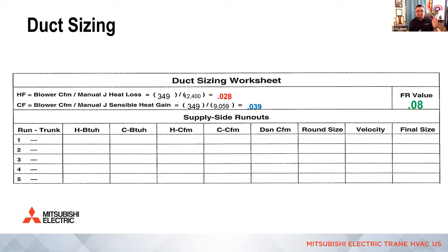Then we're just going to list the rooms that we're going to service with this air handler. So this particular unit is going to service a master bedroom, a bathroom, and then a second bedroom. So probably, let's say upstairs of a Cape style home, okay? If we have an attic above it, maybe we duct to that particular area because the loads are so low in this example. So we would list the heat loss for each room. So as an example, the master bedroom heat loss was 7,200, right? And then we list the sensible heat gain for each room. So in that example for the master bedroom, it was 4,200.